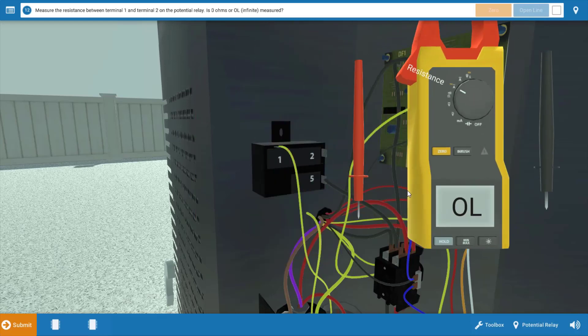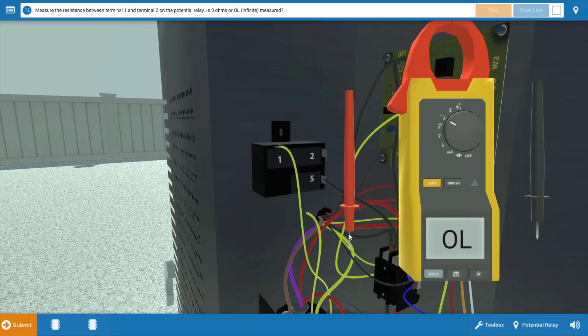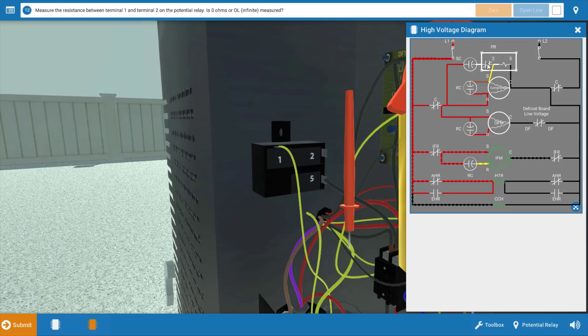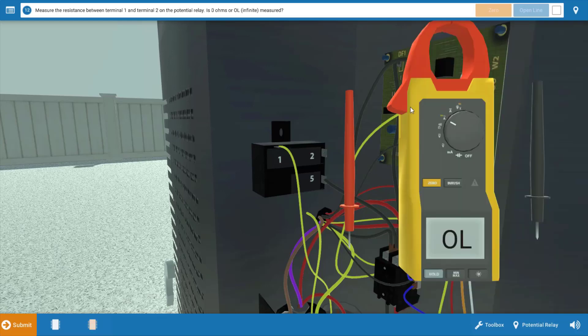Now, the potential relay has normally closed contacts. Let me show you what I mean. If we look at the wiring diagram, we can see these contacts right here between terminals one and two are in the closed position when the power's off. So with the power off, we should read zero ohms of resistance across this if it's good.